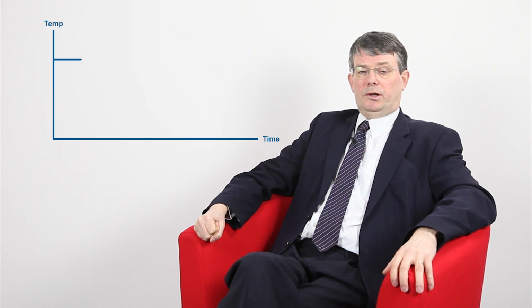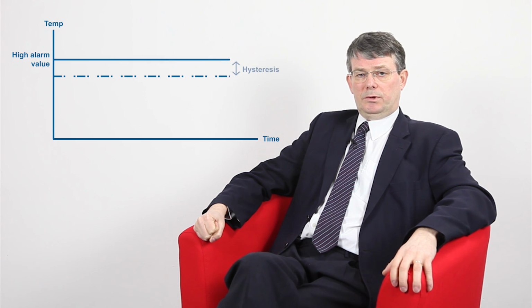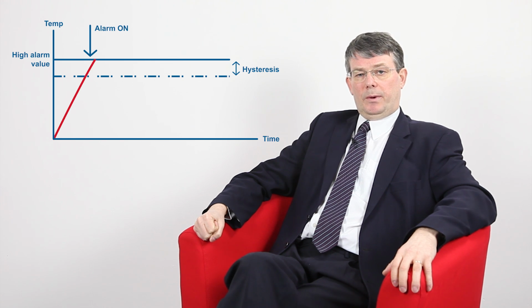Some of the models in our range have additional settings that we can use in conjunction with these alarms to tailor them more closely to our needs. First, we'll look at alarm hysteresis. Most of our models offer an adjustable hysteresis parameter for use with these alarms.